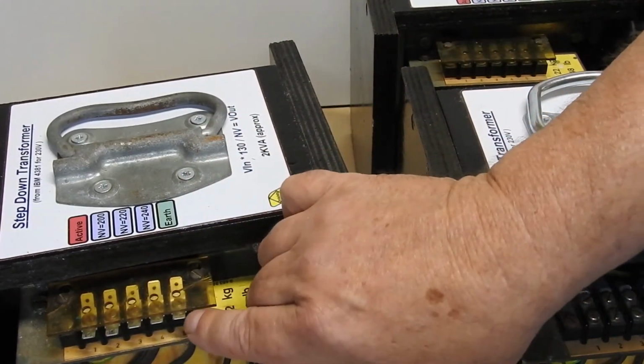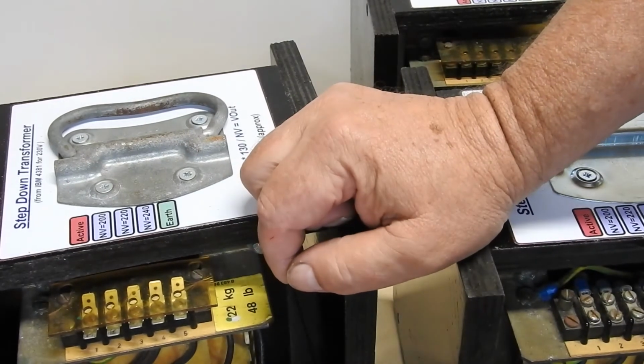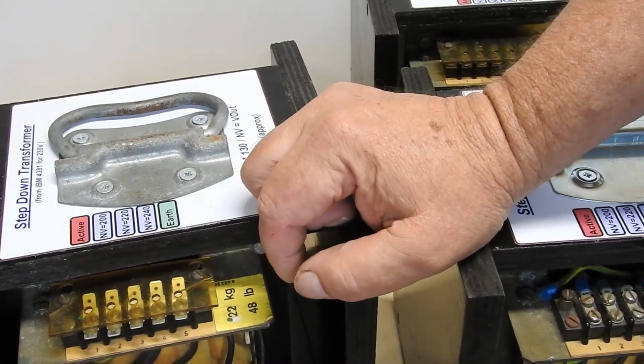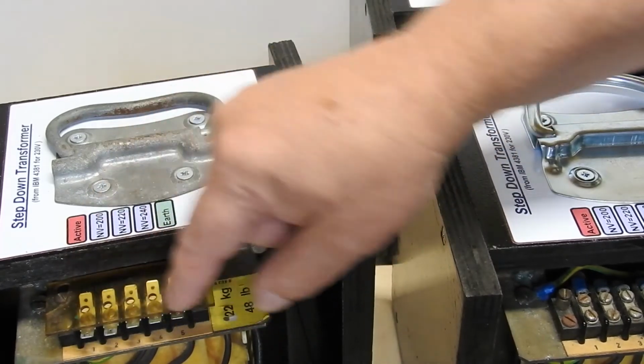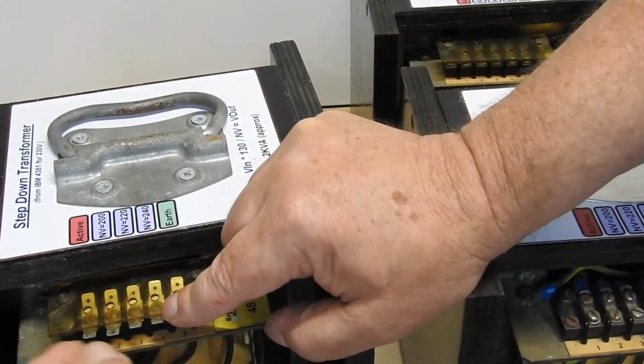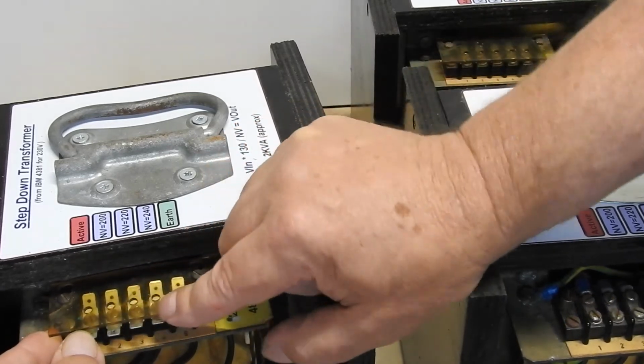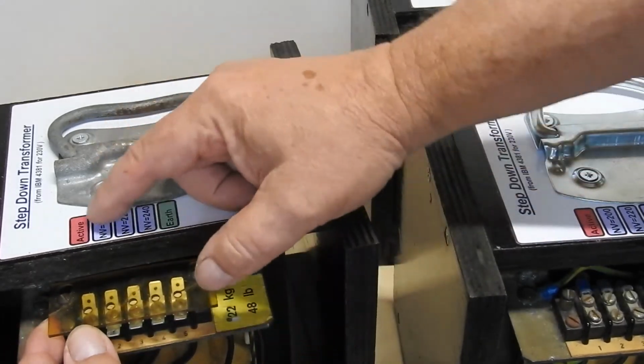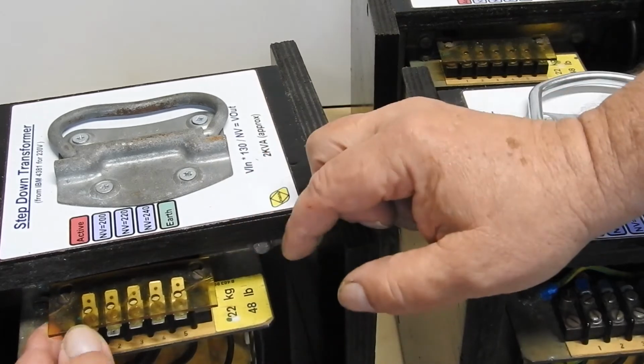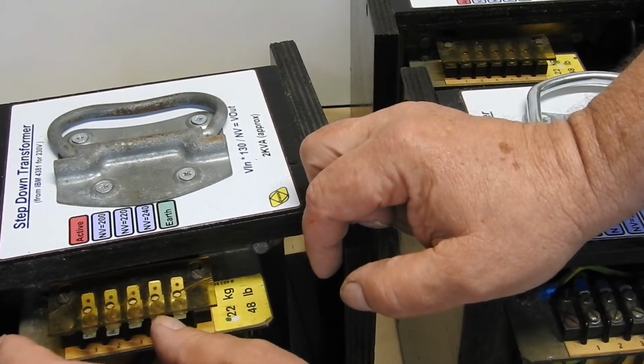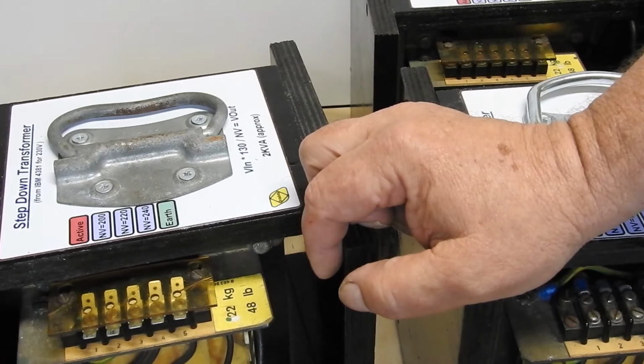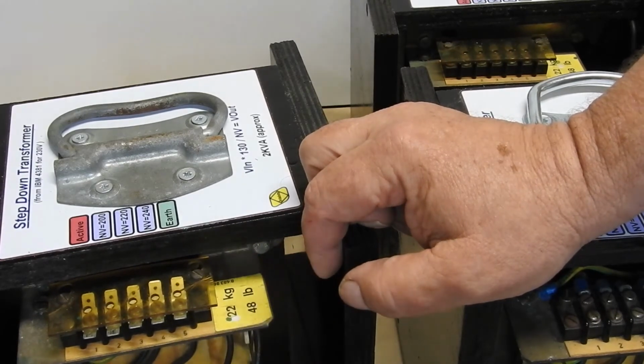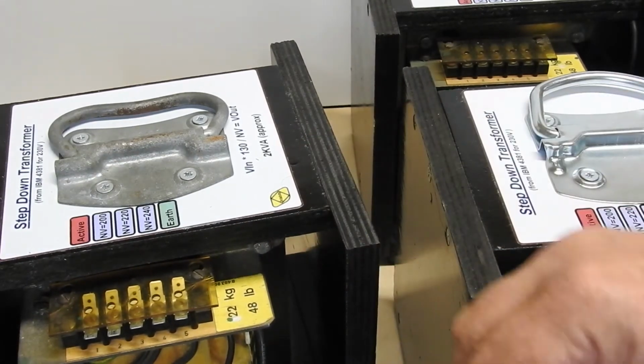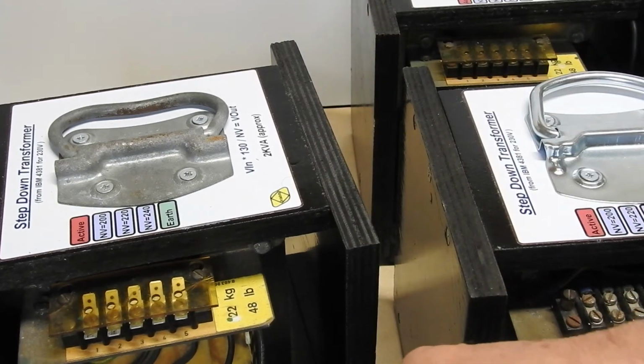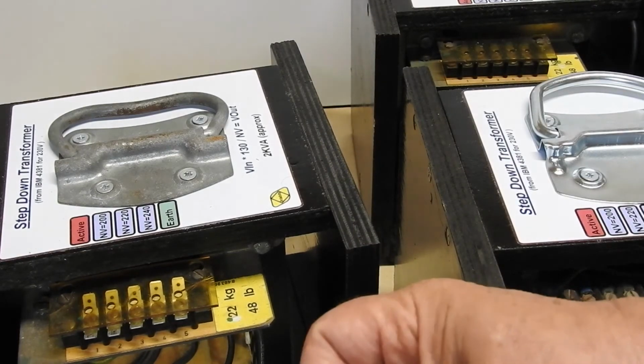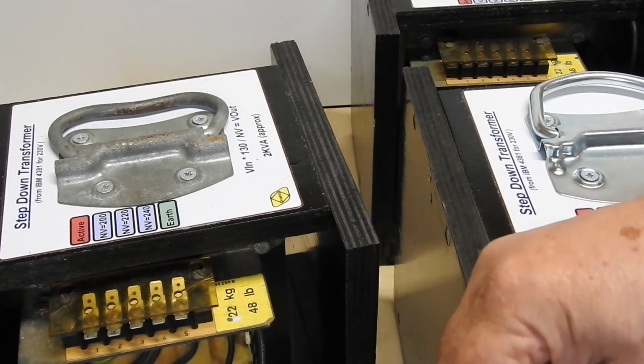There's an earth terminal there which just goes to the frame and into, I believe, an electrostatic shield inside, and a neutral connection, active and then 3 neutrals, or vice versa, but for 200, 220 and 240 volt tappings. But even at 240 volts, the output is not half, it's not 120, it's 130. Then, but maybe at full load of something like a couple of kilowatts, that might sag down to 120.